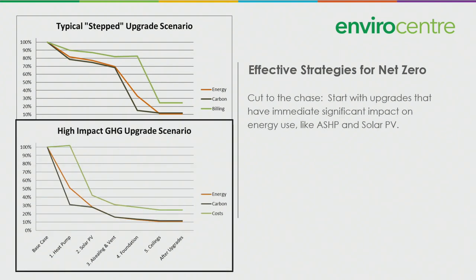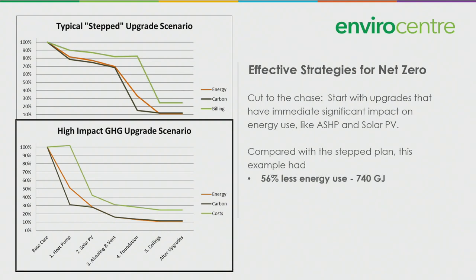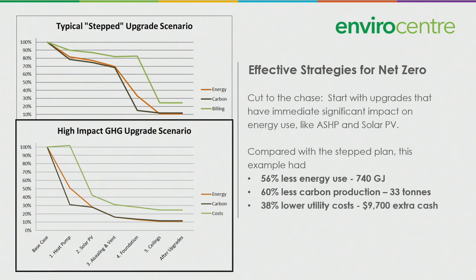What I would recommend instead are more effective strategies for net zero, including this high impact greenhouse gas upgrade scenario. With that scenario, we cut to the chase. We start with upgrades that have immediate significant impact on energy use, like air source heat pumps and solar photovoltaic cells. Compared with the step plan over a period of 5 years, this example had 56% less energy use, which amounted to 740 gigajoules, 60% less carbon production, 33 tons, and 38% lower utility costs, which amounted to almost 10 grand in extra cash. So obviously it's a better route, especially when you consider that both of these upgrades cost exactly the same amount. The capital costs were the same.